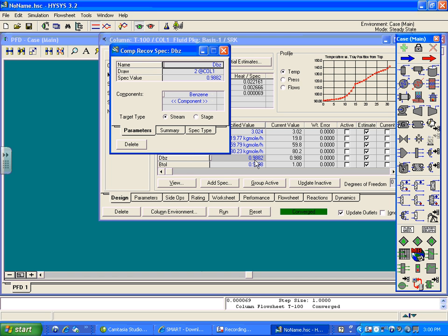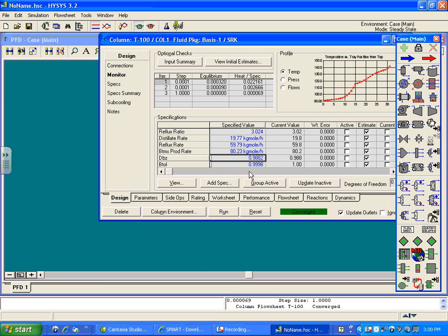By making no adjustments to the temperature set points and disturbance in the feed composition, I am getting a slight decrease in the distillate benzene recovery. If this is unacceptable, then what has to be done is take a measurement of the benzene composition in the distillate and then adjust the top tray temperature set point, T12 temperature set point. Do you see what I'm saying?